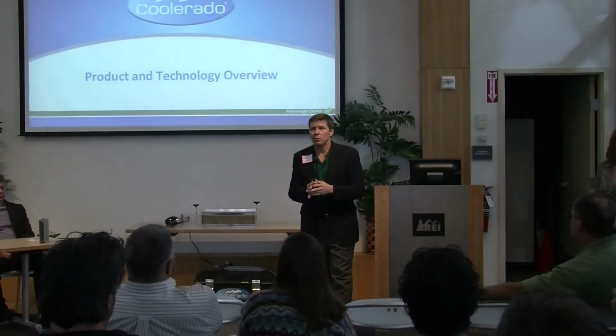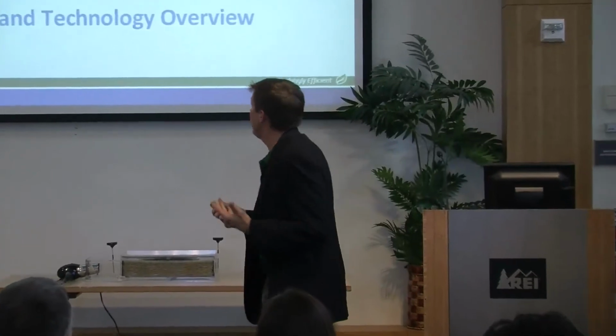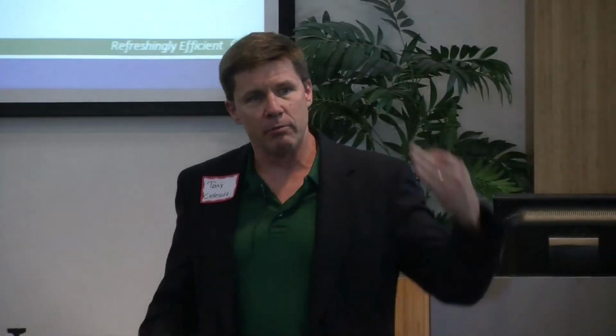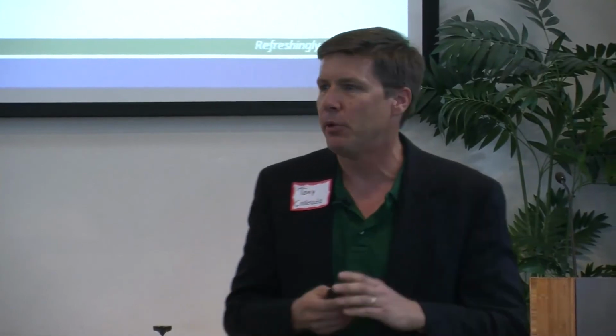Hi, Tony McDonald with Coolerado. We are a Denver-based manufacturer of an innovative and patented type of indirect evaporative air conditioning technology. So you might be familiar with a swamp cooler. A swamp cooler is a direct evaporative: warm air, wet media, cools the air, but it gives you a lot of humidity. Our technology is indirect. What it does is it cools the air, so it reduces sensible temperature a lot, but it doesn't add humidity. So what that does is open up a lot of interesting capabilities for you to do.